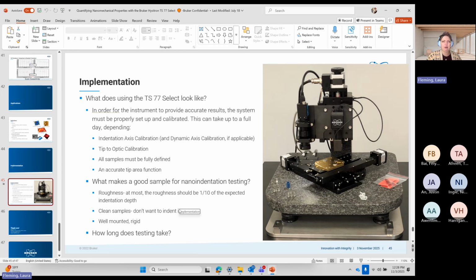That's why, instead of an SOP that says do this, do this, do this, I ask it as a series of questions: is this accurate? Is that accurate? Do you have a good tip area function? That's what we're going to cover during training: there are 5 questions we have to answer to make sure that we have set up the system well. So it can take up to a full day. You need to have your indentation axis calibration completed and your tip to optic calibration. You have to have all the samples defined, and you have to have an accurate tip area function.